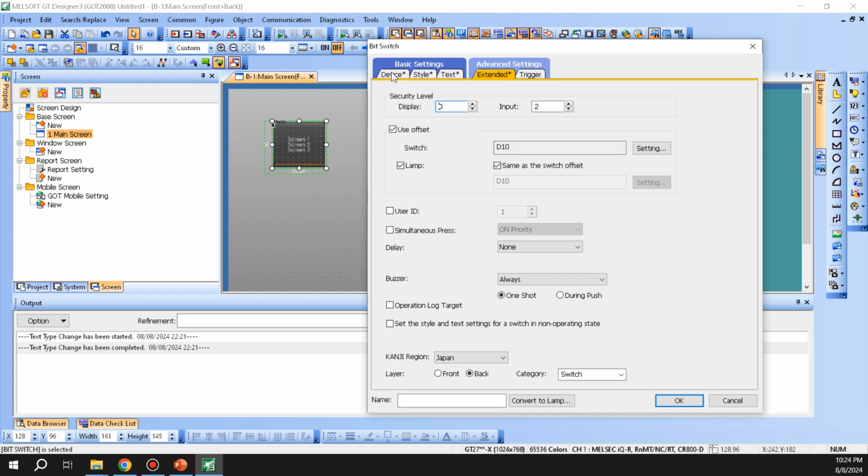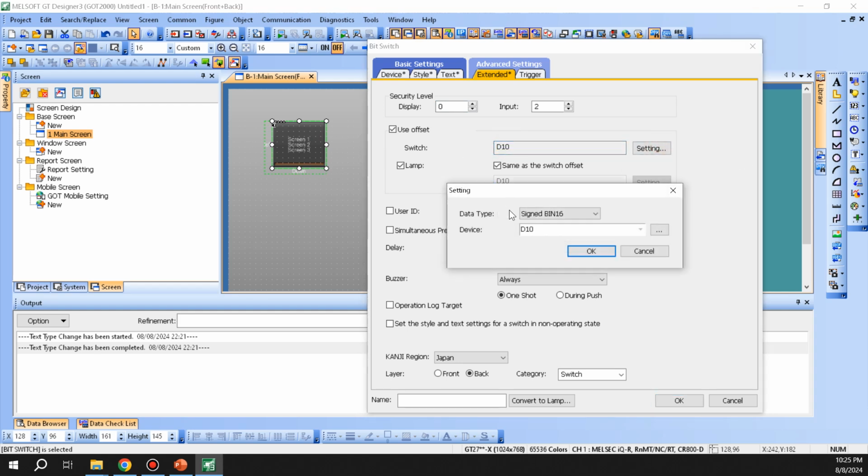It's really helpful when you have, let's say, 5 drives and you're trying to create 5 manual screens for it. If you program your PLC such that all the memory is grouped together for each drive, you create one screen and use an offset register. I like to use an offset from the HMI, like a GD memory is what I would use for it. So if I go back to this, use a GD for that.